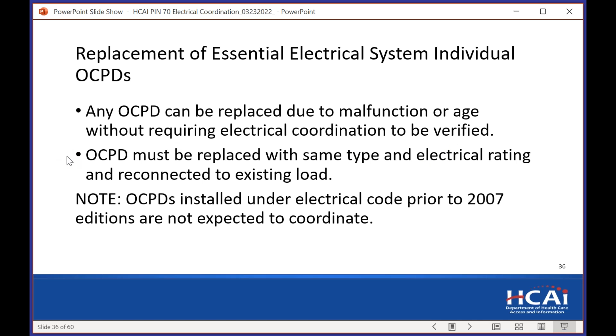So, replacement of essential electrical system individual OCPDs. You have a bad breaker in a panel due to age, you can replace it. We're not going to require coordination to be verified. You're replacing it with the same size, the same rating, the same type of breaker. We move forward. We want you to replace bad equipment.